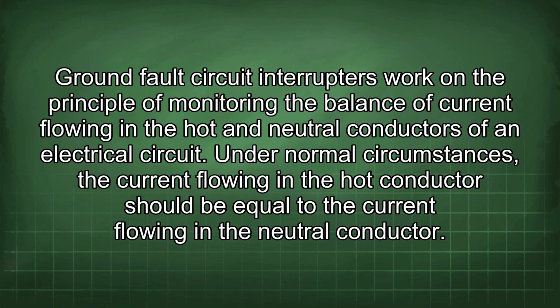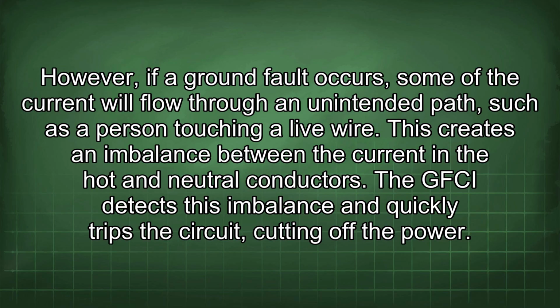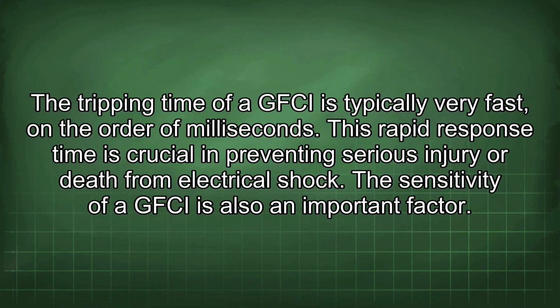Ground fault circuit interrupters work on the principle of monitoring the balance of current flowing in the hot and neutral conductors of an electrical circuit. Under normal circumstances, the current flowing in the hot conductor should be equal to the current flowing in the neutral conductor. However, if a ground fault occurs, some of the current will flow through an unintended path, such as a person touching a live wire. This creates an imbalance between the current in the hot and neutral conductors. The GFCI detects this imbalance and quickly trips the circuit, cutting off the power. The tripping time of a GFCI is typically very fast, on the order of milliseconds. This rapid response time is crucial in preventing serious injury or death from electrical shock.